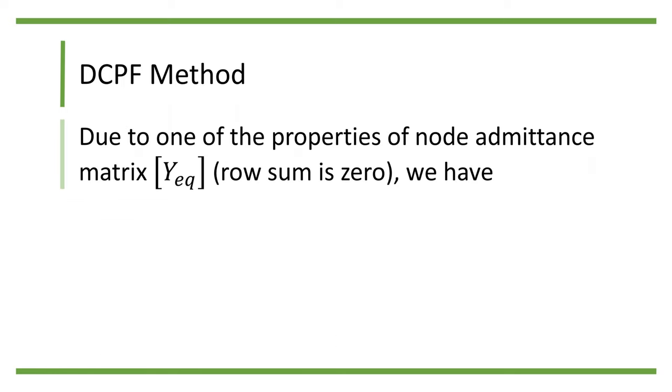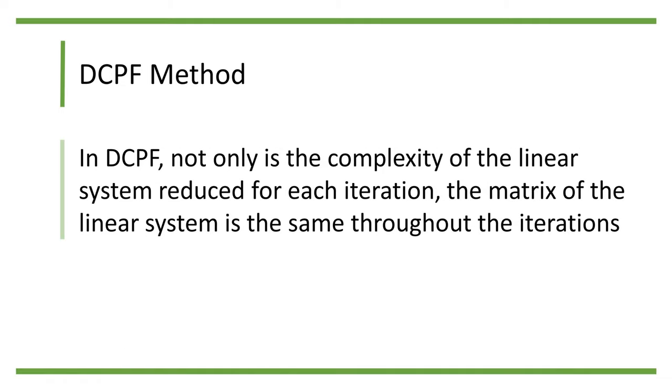Due to one of the properties of node admittance matrix Yeq, that is, the row sum is 0, we have partial Pi partial theta k and partial Qi partial uk both approach y bar ik. So in DCPF, not only is the complexity of the linear system reduced for each iteration, the matrix of the linear system is the same throughout the iterations.